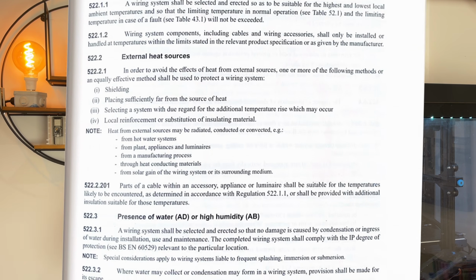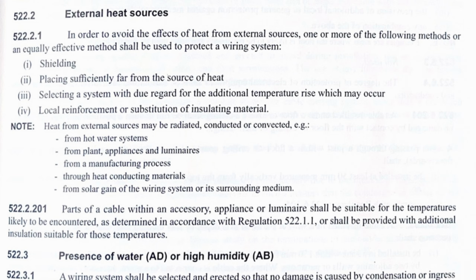522.2.1 touches on protecting cable against heat damage. Remember, heat damage is going to cause a higher resistance, which will cause heat, which will ultimately cause the cable to be damaged to the point of fire. A lot of the regs cover the conditions that the wiring is going to face. Things such as temperature, moisture, or sunlight. These are just a few.